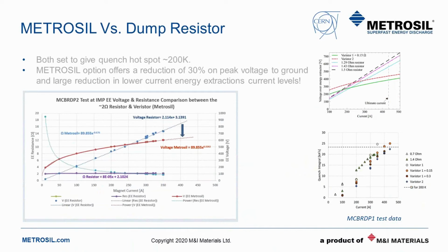But they have also taken on to use the METROSIL in part of their test facility. On the right hand side, the bottom graph has current on the x-axis and quench integral on the y-axis. You could also think of this as hotspot temperature, with the dotted line being our target maximum value. You can see the string of small green triangles - these were resistor values, and the bottom values would be the equivalent Varistor or METROSILs, which Tom mentioned earlier. You can see there's a considerable reduction in the hotspot.